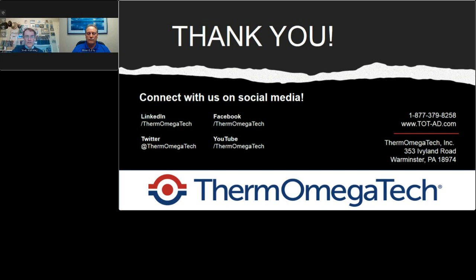What sort of lifetime, as in number of cycles, do you typically expect out of a thermal valve? So from previous cycle testing, we've done at least 150,000 cycles. Now, bear in mind, that's on the thermal element itself, cycling 30 seconds up, 30 seconds down, continuing until the thing would actually die. But that's a very, very extreme case. For thermal bypass valves and thermal mixing valves, they tend to sit there and dither back and forth, only using up a fraction of the available stroke. So they tend to last a lot longer, upwards of like 10 years, I'll say.